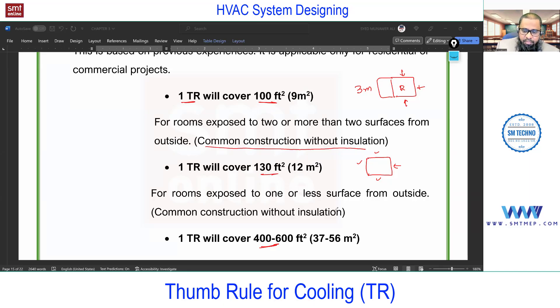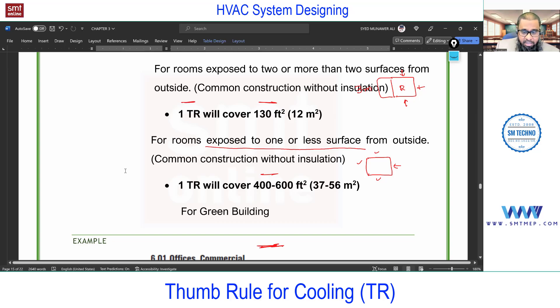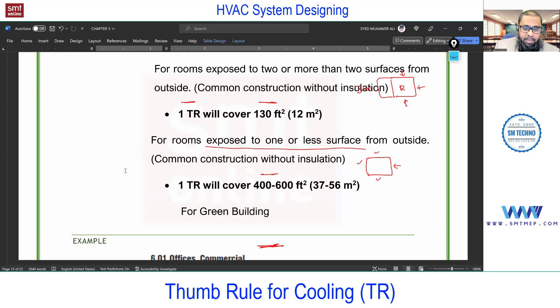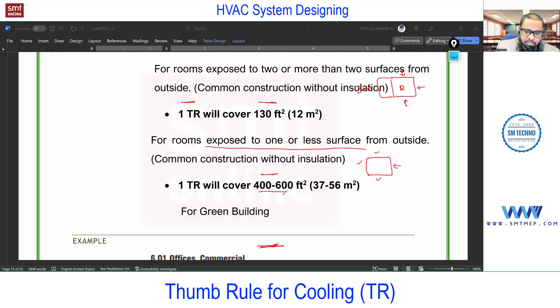In actual practice now, 1 ton of refrigeration covers 400 to 600 square feet for a standard insulated building, also referred to as a green building or standard project. High-class projects include insulation in walls and roofs. Even for small projects in India, roof insulation is common since the top slab is exposed to the sun. For a green or standard insulated building, 400 to 600 square feet per ton is the current rough estimate.